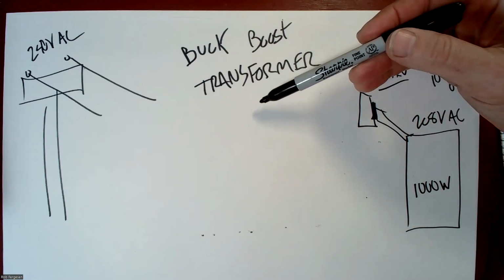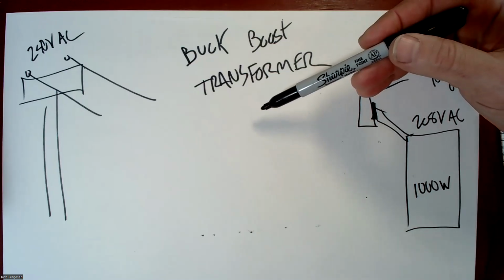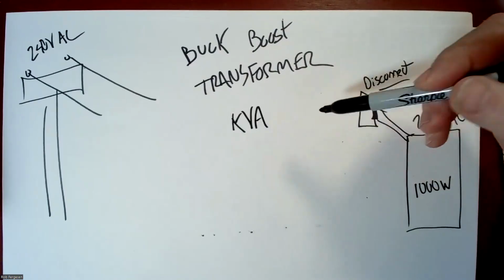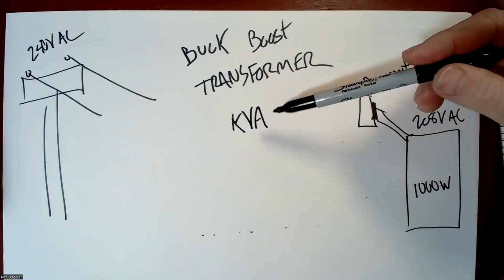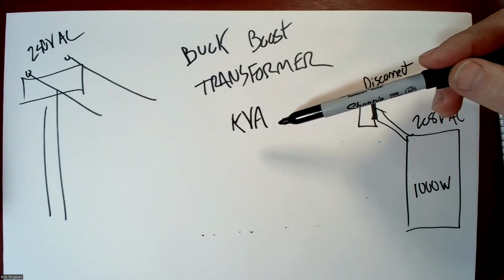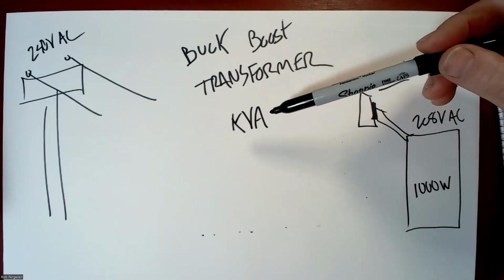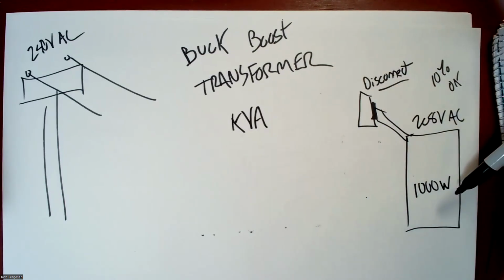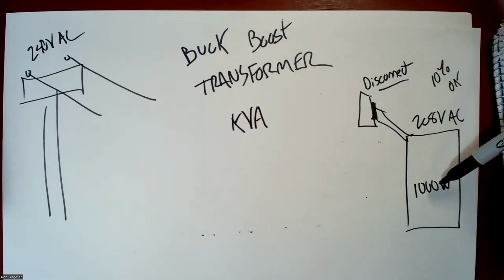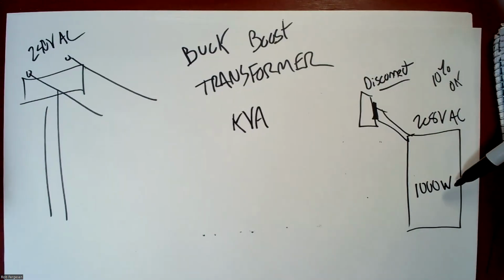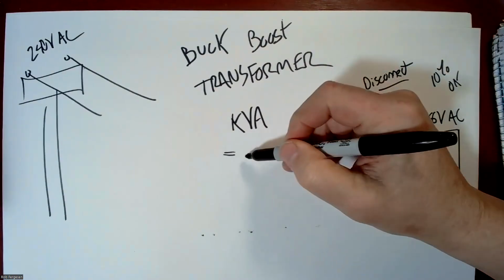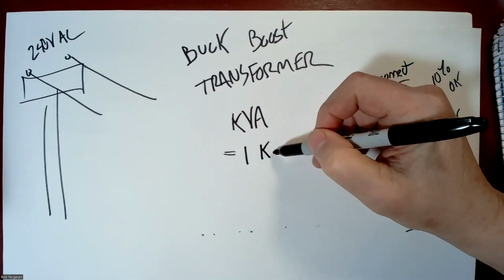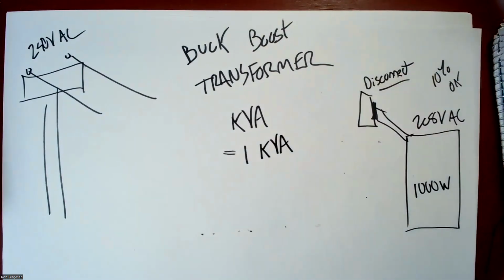Transformers are sized based on what they call kVA, or thousands of volt amps, kVA. So voltage times the amperage, P equals IV. So amperage times voltage is the same thing as power. So a 1,000-watt single phase circuit is simply equal to 1 kVA, or 1,000 volt amps.